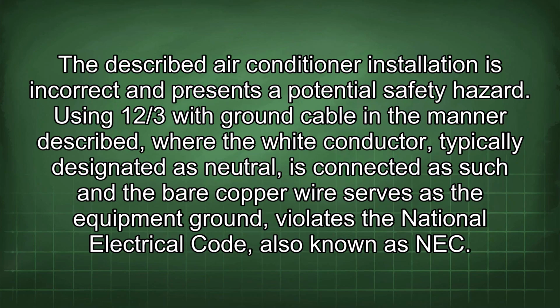The described air conditioner installation is incorrect and presents a potential safety hazard. Using 12/3 with ground cable in the manner described, where the white conductor, typically designated as neutral, is connected as such and the bare copper wire serves as the equipment ground, violates the National Electrical Code, also known as NEC.